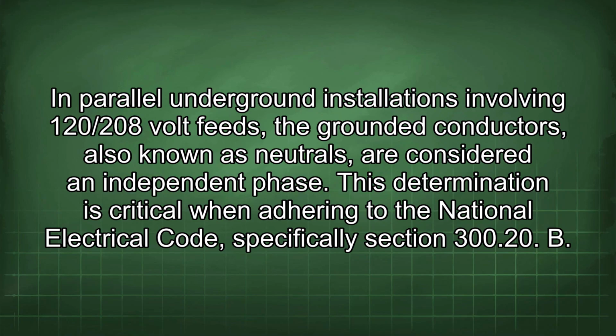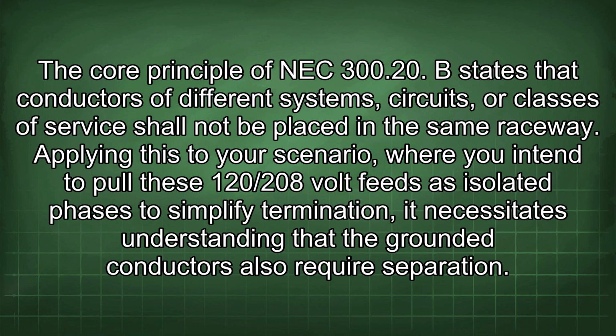parallel underground installations involving 120/208 volt feeds, the grounded conductors, also known as neutrals, are considered an independent phase. This determination is critical when adhering to the National Electrical Code, specifically Section 300.20. The core principle of NEC 300.20 states that conductors of different systems, circuits, or classes of service shall not be placed in the same raceway.